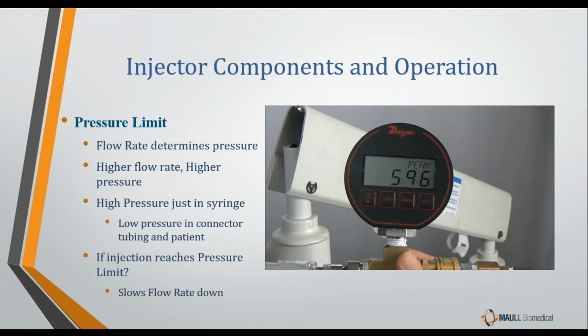And what does that do? Now those blood vessels don't show up as nice, bright white areas on the image. They're darker because not as much contrast is in the region of interest. More X-rays are penetrating the blood vessels, so the blood vessels are too dark. So if that's the case, then we have to go back and fix that injection. So now we have to fire the patient up again with another X-ray image. Because the operator did not understand pressure limiting, and they set the pressure limit lower than it was supposed to be set, now we have to hit the patient again with another X-ray, which is just added needless patient dose. So that's why it's important that the operators understand the purpose of pressure limiting and how to use it. And again, the vast majority of them do, but every now and then you run into one that doesn't. They think they know what they're doing with the pressure limiting, but they don't quite understand it.